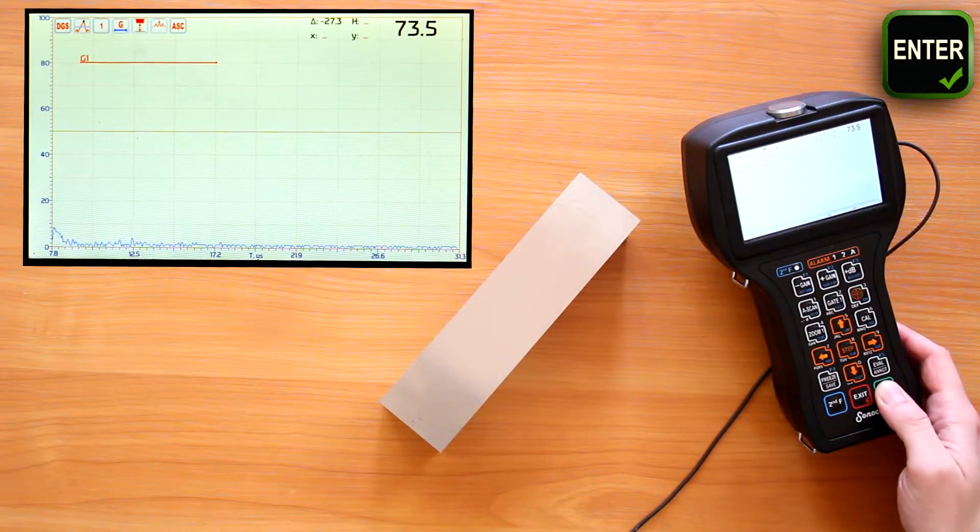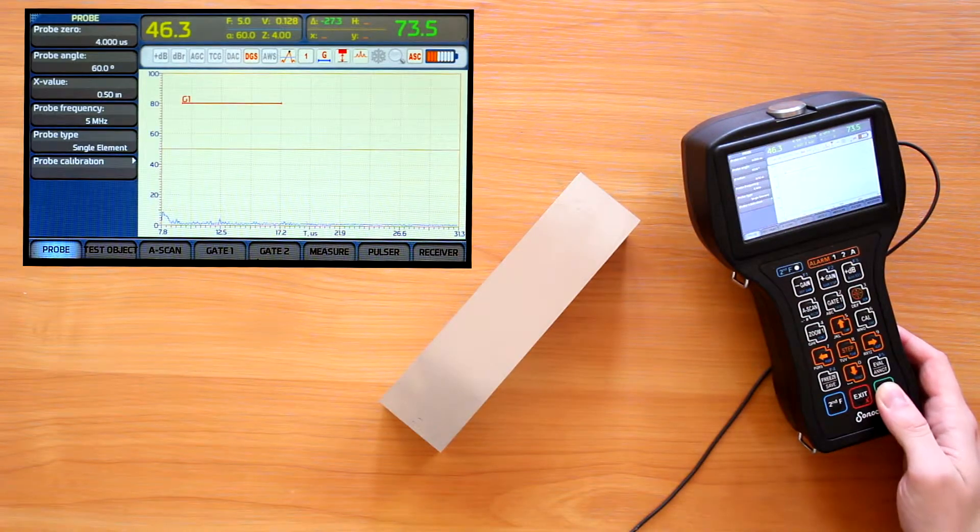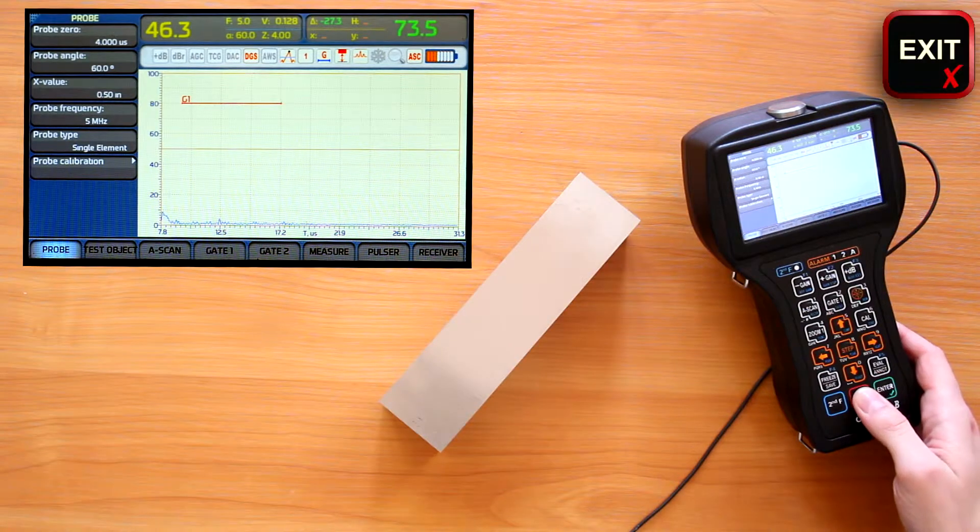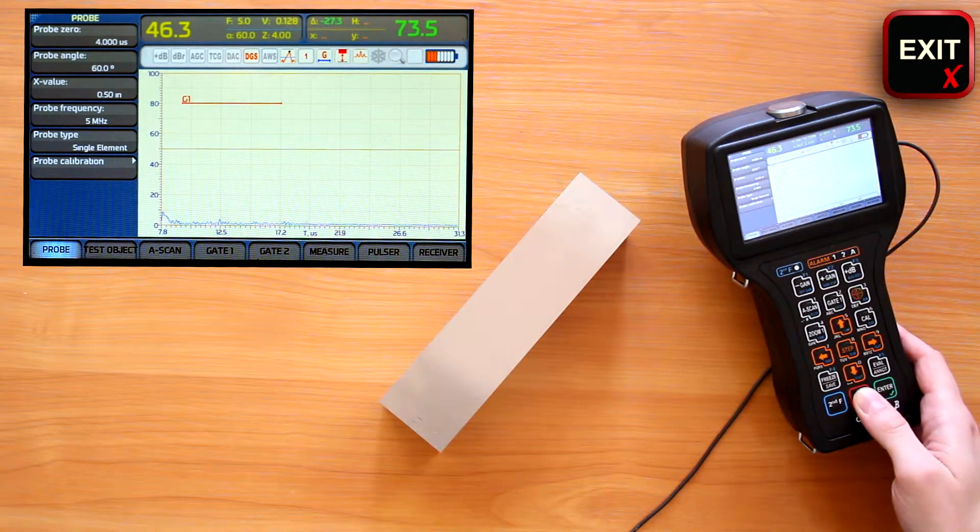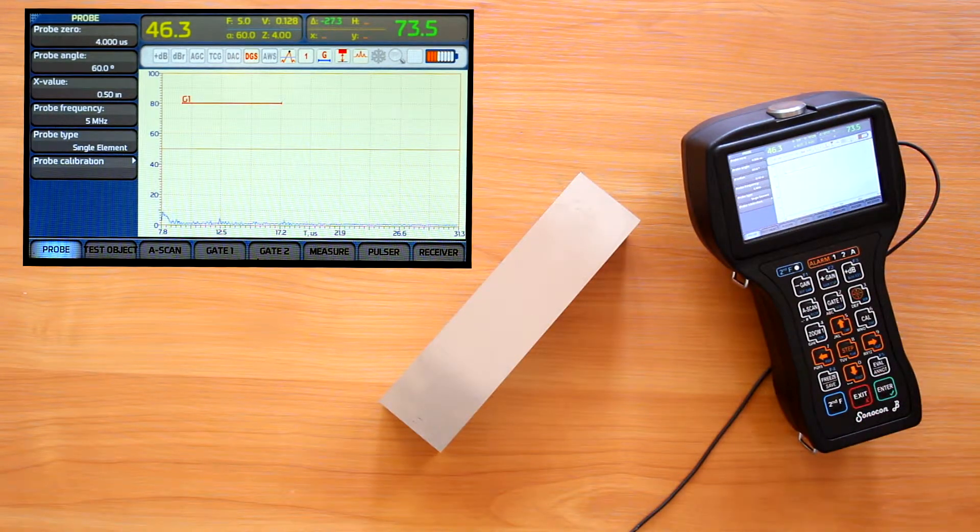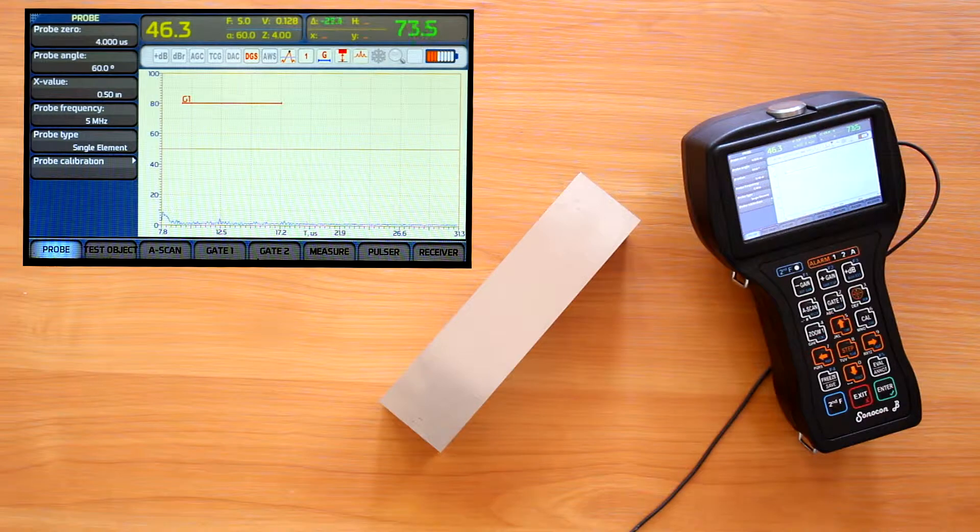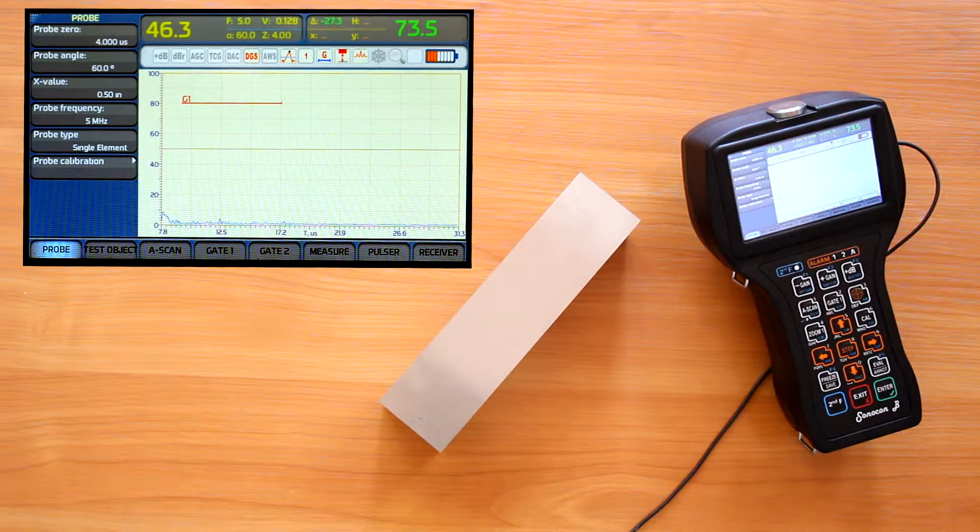Enter button would switch A-scan between full screen and normal modes. To exit the A-scan direct control mode, we can press exit button. After A-scan is set up, now we are ready to set up gates.